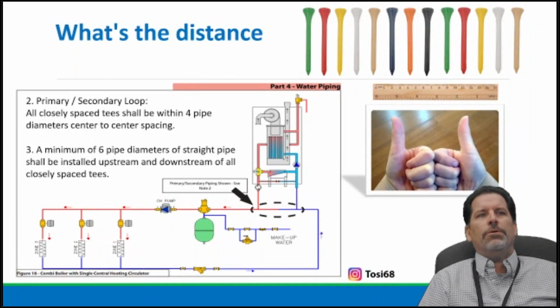We might have issues with delivery, or the boiler going off on some safeties, improper flow in and out of the boiler. Water slows down, we go off on a safety, a high limit. We're stacking temperatures in that heat exchanger, and it protects itself, it shuts down.